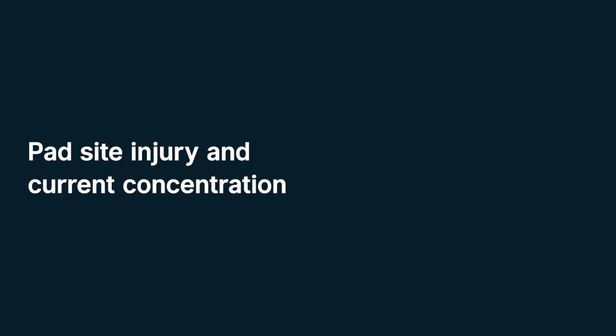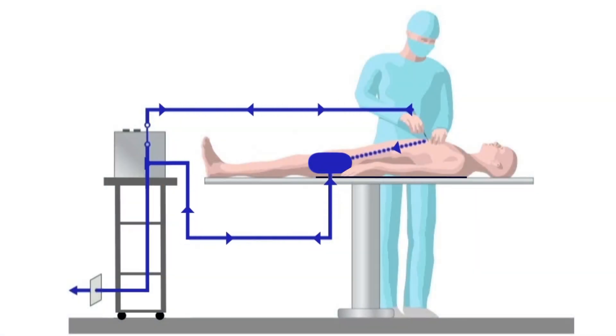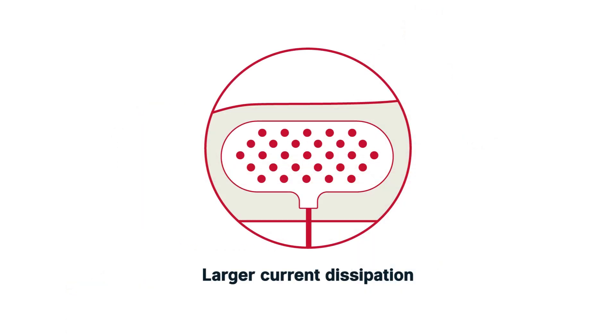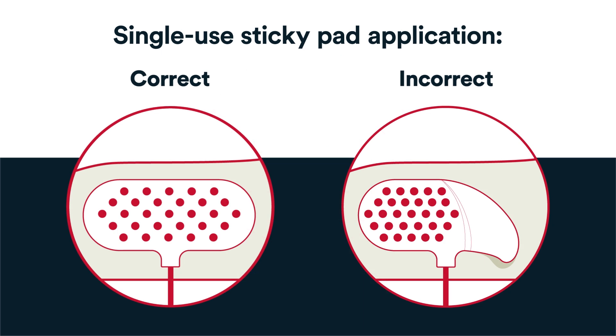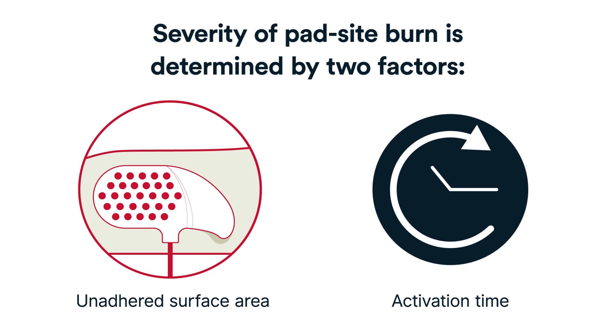Pad site injury and current concentration. As alternating current enters and exits the patient, the return electrode size is key to preventing unintended tissue damage to the skin in contact with it. Return electrodes can be a single-use sticky pad or a large reusable pad. The large surface area dissipates electrical current to reduce energy density and avoid tissue damage. When a single-use sticky pad is incorrectly applied, it can cause a pad site burn. The degree of tissue damage or severity of the pad site burn is determined by two factors: unadhered surface area and activation time.